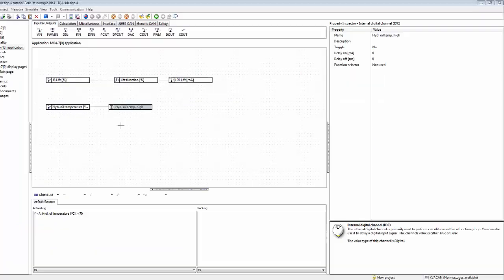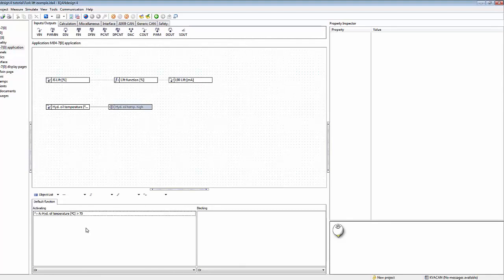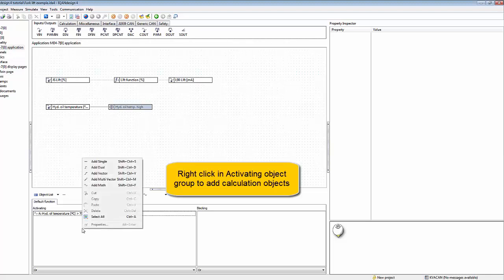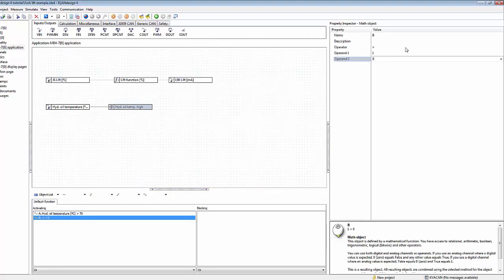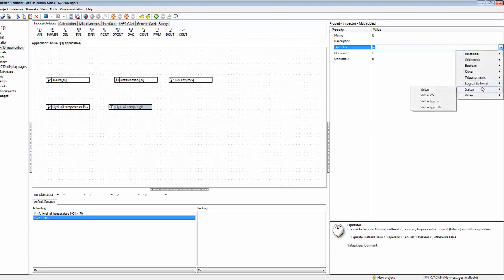The idea with object list is that it's a list of conditions that are combined with method. So we have another condition here for this error, and that is that the status of the input is in low error. We can right-click here and add math, and we select the operator here to be status equals.